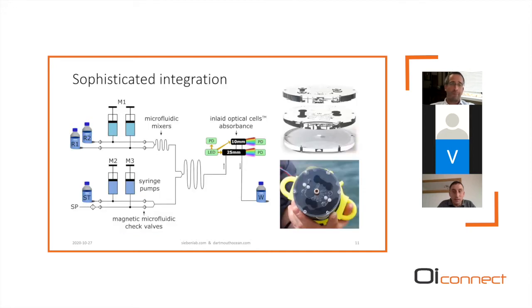And finally, when we're heating a fluid, ultimately we're down to a few microliters or fractions of a raindrop. We really don't want to spend energy heating up a block of the chip. We're really only trying to heat up a small portion of that channel. So we really want to bring that heater as close as possible. And so we've integrated wires and deposited thin film heaters close to our channels. We've done some very innovative insulating techniques that we're in the process of writing up and patent protecting, so I can't get into too many of the details here, but we've been able to go from kilojoules per sample, essentially, when we just heat the block or the chip, down to tens and hundreds of joules, which is just highly advantageous.